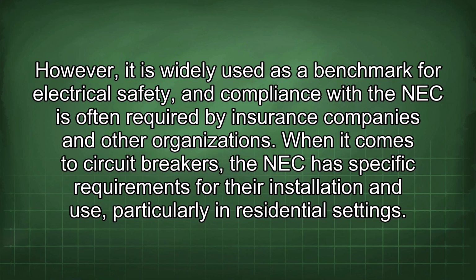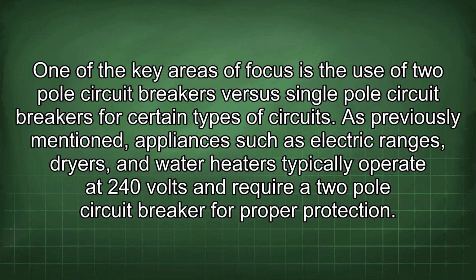When it comes to circuit breakers, the NEC has specific requirements for their installation and use, particularly in residential settings. One of the key areas of focus is the use of two-pole circuit breakers versus single-pole circuit breakers for certain types of circuits. As previously mentioned, appliances such as electric ranges, dryers, and water heaters typically operate at 240 volts and require a two-pole circuit breaker for proper protection.